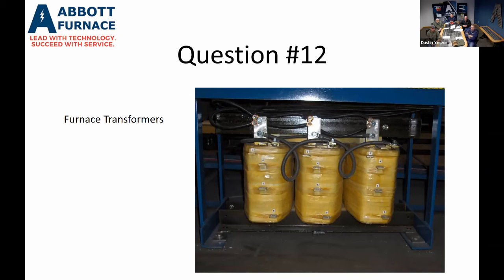If the glow bars are getting imbalanced, where somebody, like we mentioned before, would put one glow bar in a zone, then you start getting what they call an imbalance. And you'll start seeing an imbalance in your current and also in your voltage between banks, between legs. If you have that, going up a tap is not going to help you. You're going to start damaging equipment, mainly SCR fuses. You'll start blowing fuses on your SCRs if you don't have a proper balance on your zone.